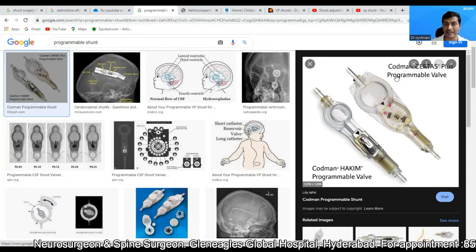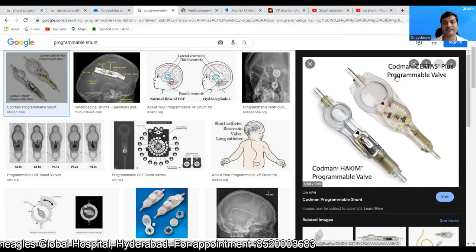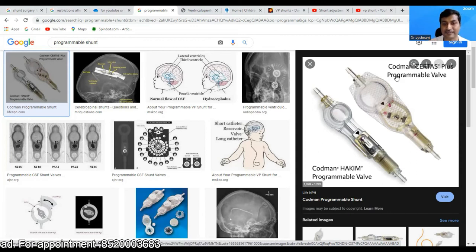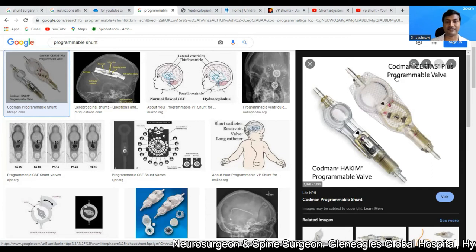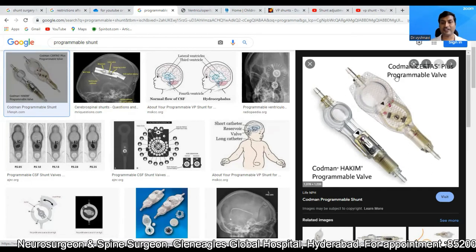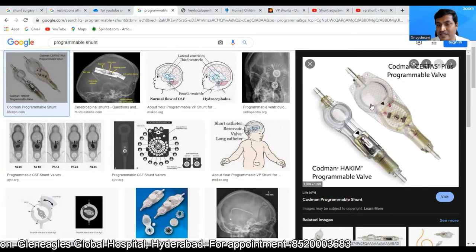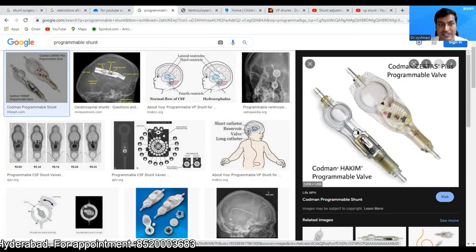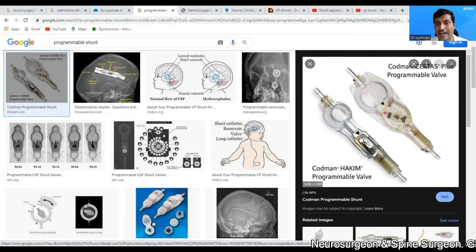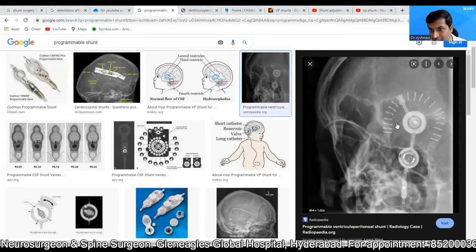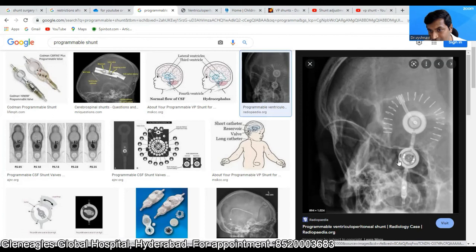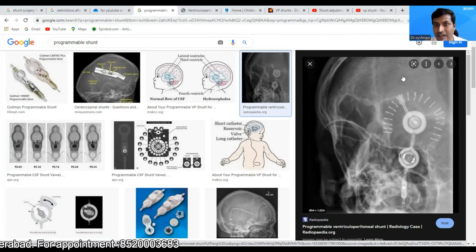If you put a fixed pressure shunt in these patients and the shunt over-drains or under-drains, you will have to revise the shunt — placing one with a higher or lower pressure. To circumvent this, we have a programmable shunt. This valve is programmable, meaning the pressure can be adjusted externally without surgery.